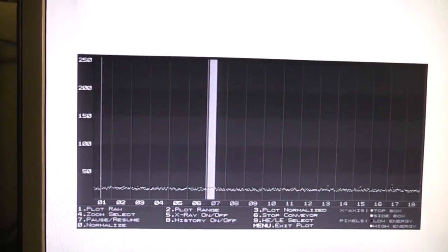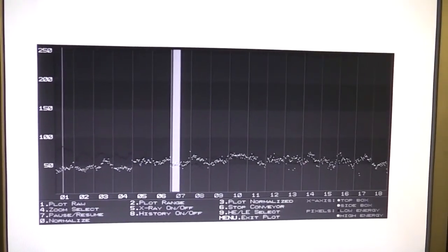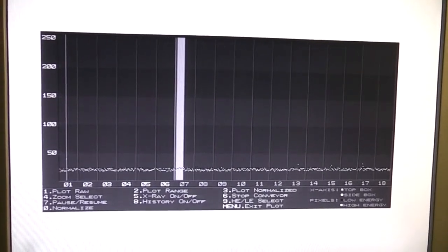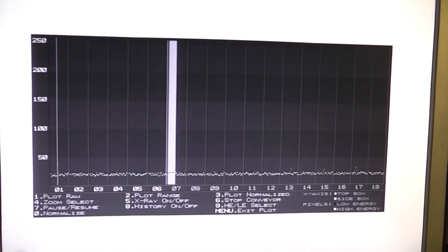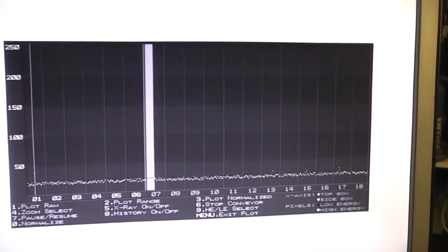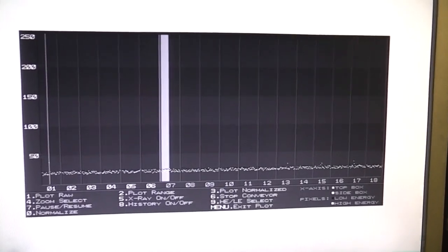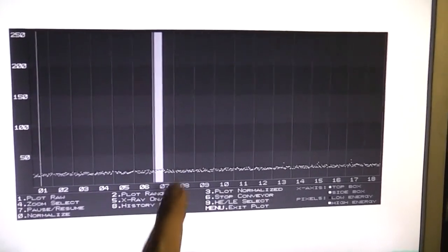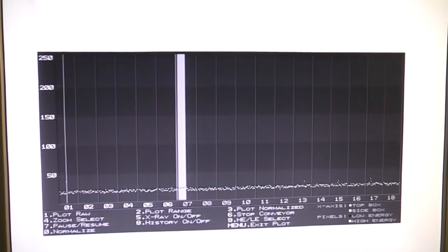So I'll just slide the box back in and see what happens. Right, so I'll just turn the x-rays on and we've still got variation, but it's much, much smoother, much less variation than we had before. So we've still got this sort of vertical stripe here. Not quite sure what's going on with that. This stripe does seem to be associated with the state of the detector. For example, when I powered it up with the box open and light on it, I got loads and loads of stripes. So maybe it's either out of range, showing that the data that it read was out of range, or some sort of overflow error or something.